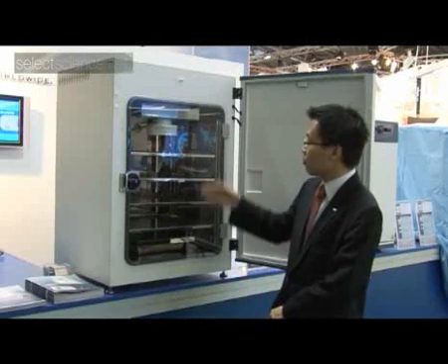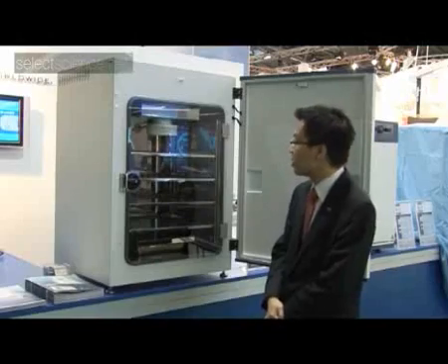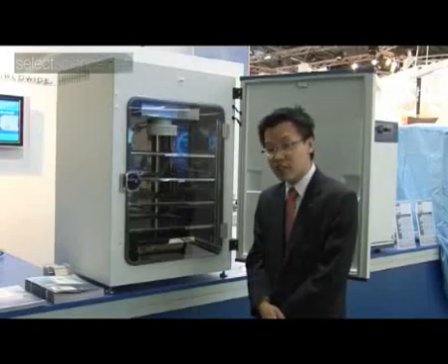We have an ULPA filter that's 10 times more efficient than the typical HEPA filters used in the industry. The ULPA filter enables the incubator to recover to ISO class 5 clean air conditions rapidly following a door closing, and this helps to prevent contamination from occurring.